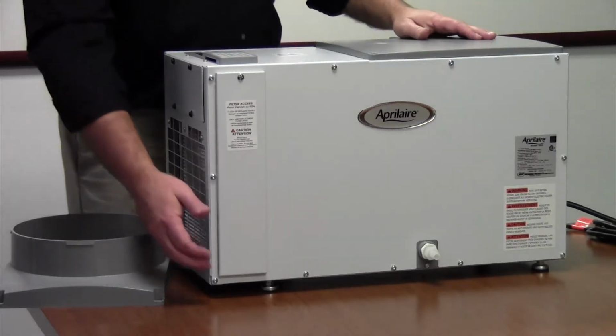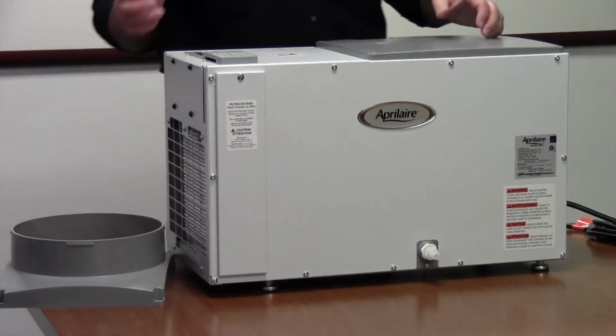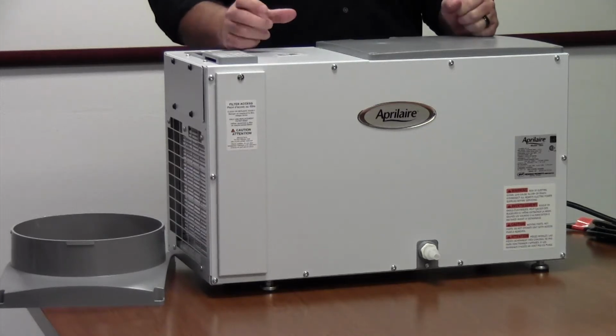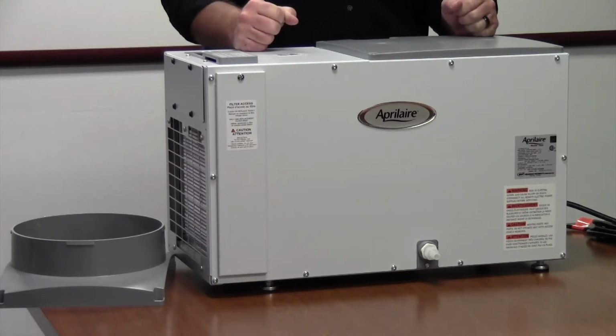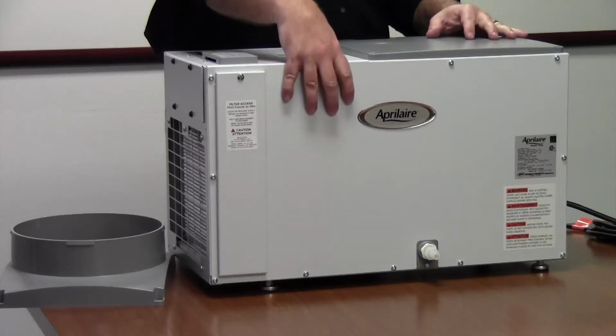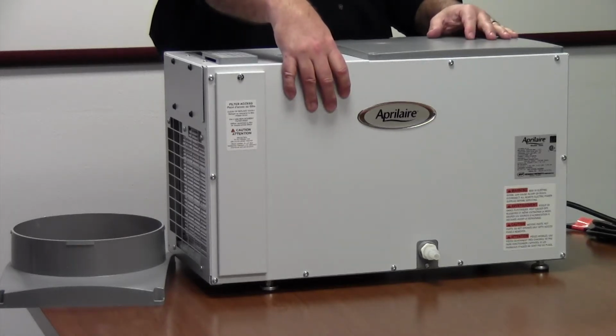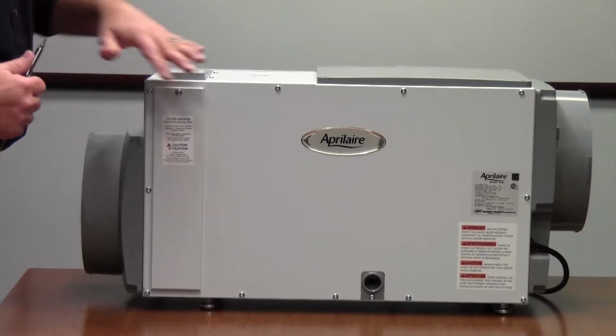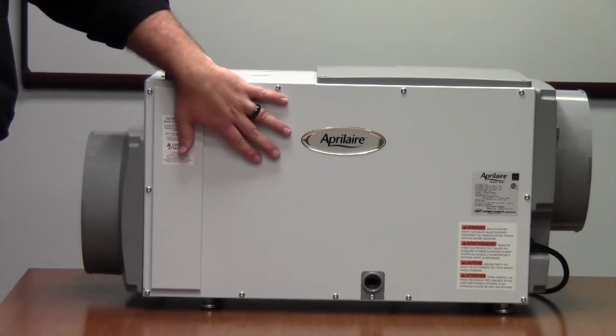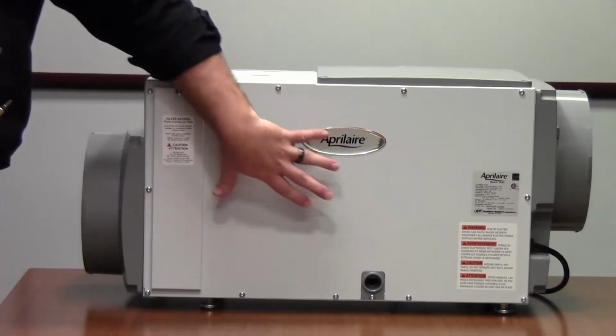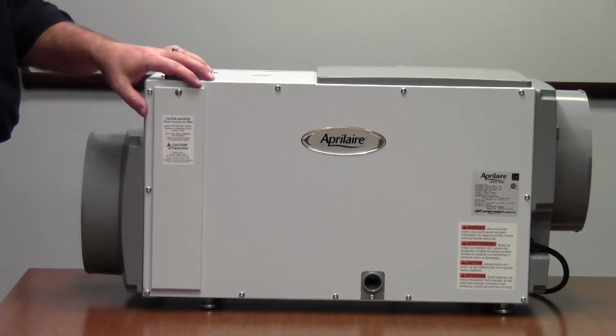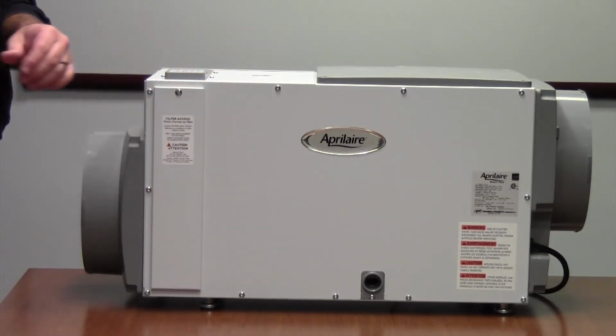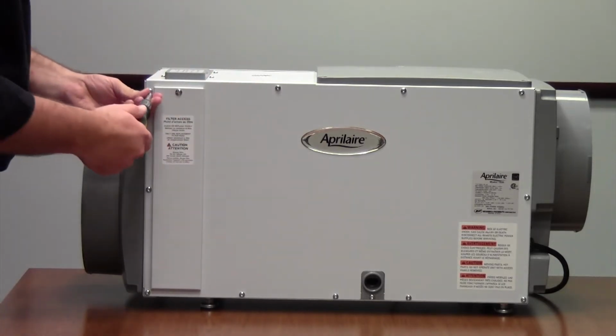We've improved on the feet of the unit, the leveling feet, to make them a lot stronger. Big plastic feet on there that are very strong. And we've E-coated the coil for corrosion resistance. Now I'm going to remove this side panel. If we could keep this panel, this side with the drain, open for service, that would be the best, because that's where everything that we should need to get to is. So I'm going to remove that panel.